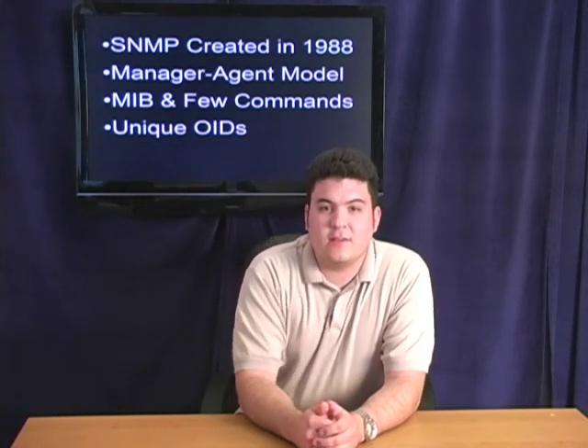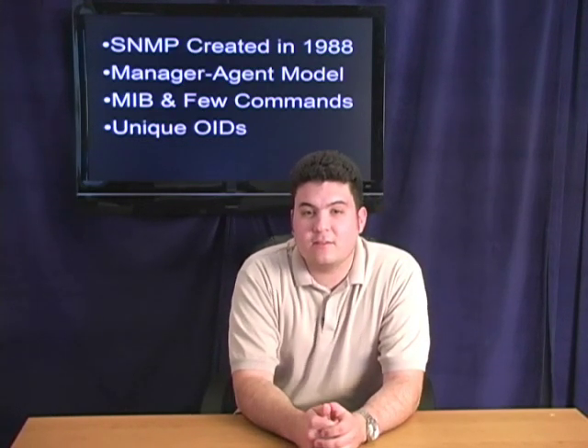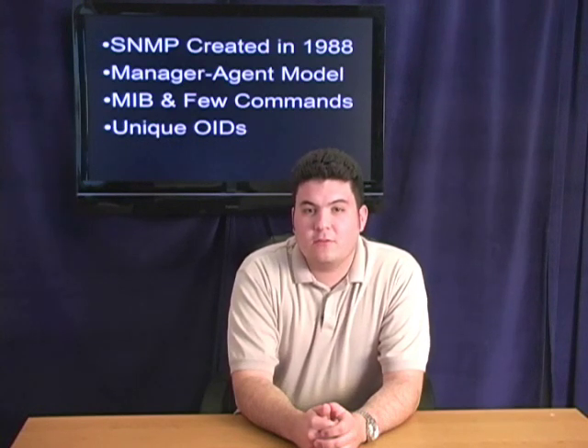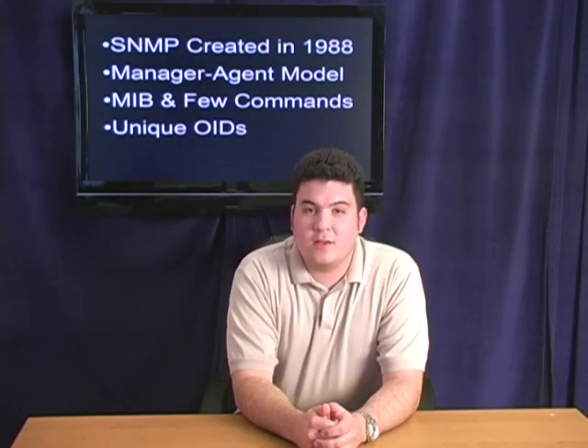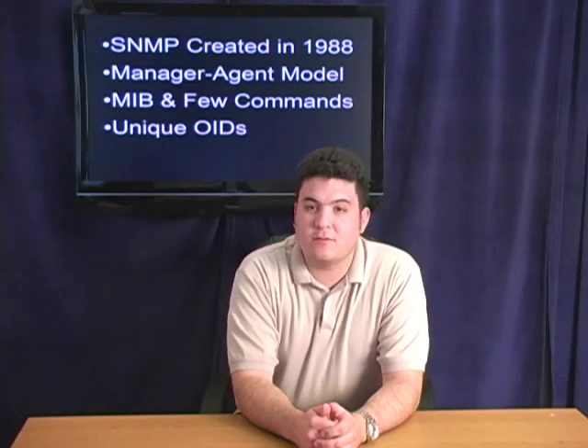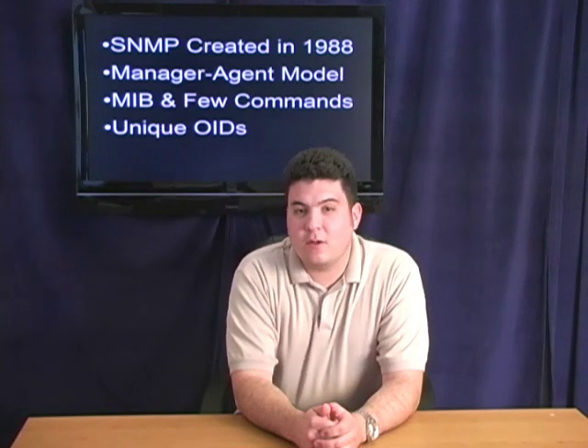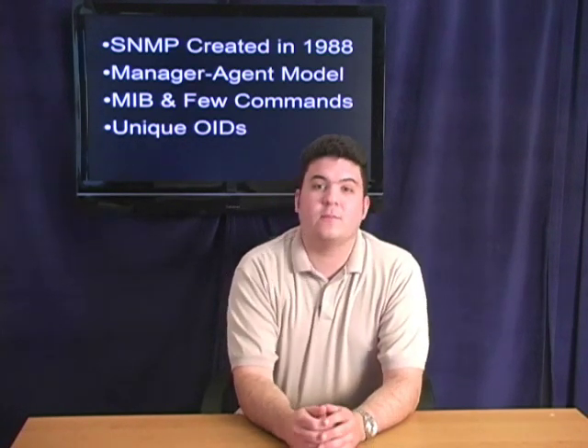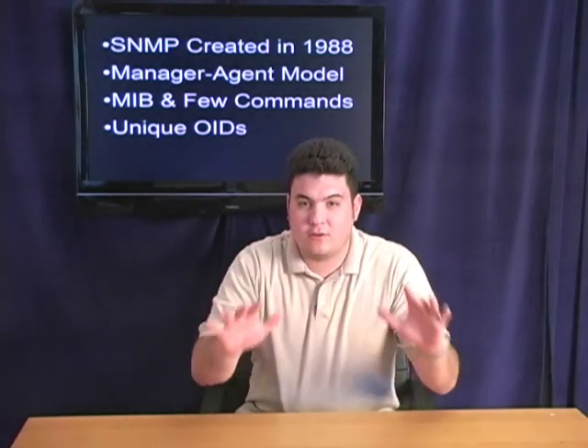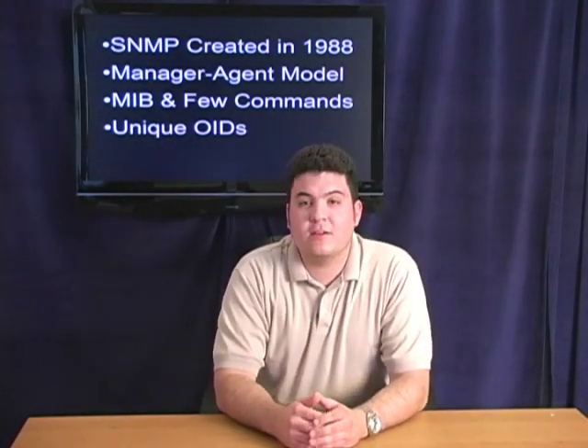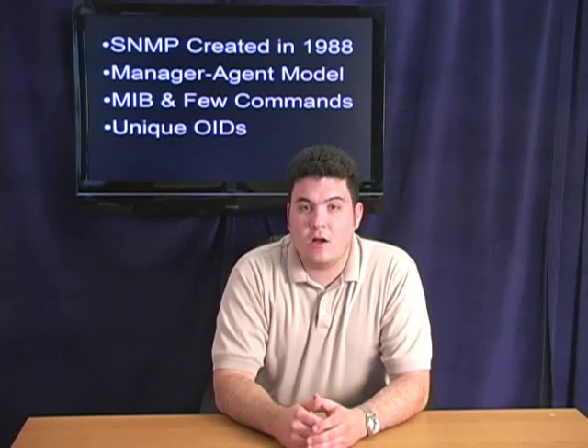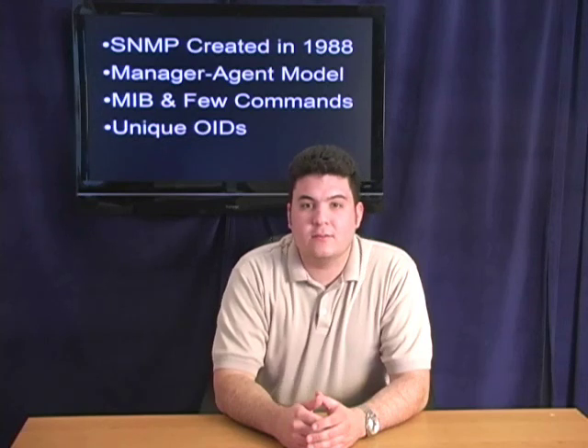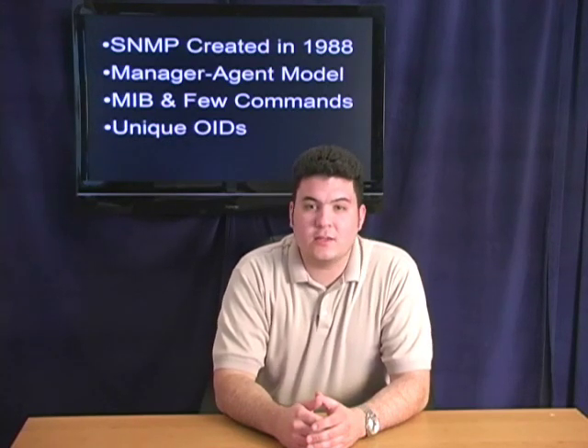The agent provides the interface between the manager and the physical devices being managed. The manager and agent use a Management Information Base, or MIB, and a relatively small set of commands to exchange information. The MIB is organized in a tree structure with individual variables, such as point status or description, being represented as leaves on the branches. A long numeric tag or object identifier, or OID, is used to distinguish each variable uniquely in the MIB and in SNMP messages.